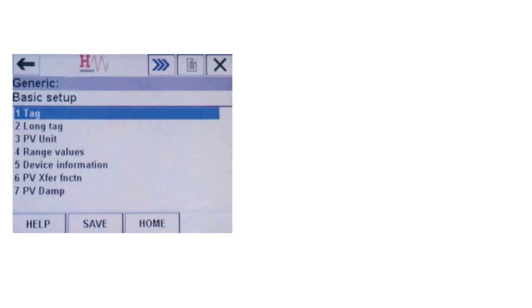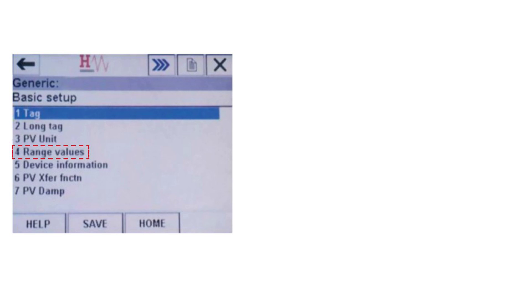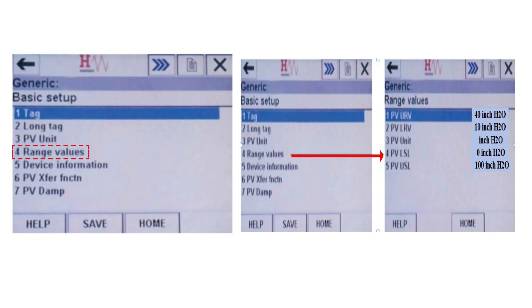As you can see, the basic setup option provides menus to change HART descriptive tags, unit of measure, range values, and primary variable damping value. Now select the range values option and press the enter button. As you can see, the range values menu has different options such as upper range value, lower range value, unit of measure, and upper and lower sensor limits. Select PV-URV and PV-LRV menu to bring up the edit screen.